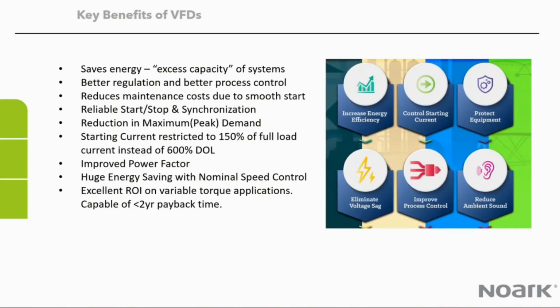The benefits of a VFD: saves energy. A lot of times today, people will run at a size that's big just to make sure they covered themselves, and it really is inefficient and keeps a lot of energy tagged for that application. Better regulation and process control. With traditional methods, you don't have process control, or if you do, it's pretty crude and not very efficient. Much better regulation with the VFD.